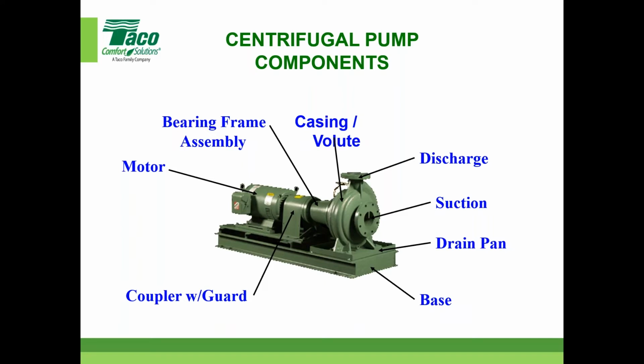But here's another question along those lines, and this is a great question. Is there any benefit to adding spring isolators to bases after grouting the base, or does grouting the base eliminate the need for spring isolation? There are actually 2 separate topics going on here. The main reason for grouting the base is to stiffen the base so that we add rigidity to the base. And that way, when the pump and motor are bolted down, taking into consideration, like Brett said, the motor shaft, the pump shaft, the coupling, the base, the grout, that's all one unit.